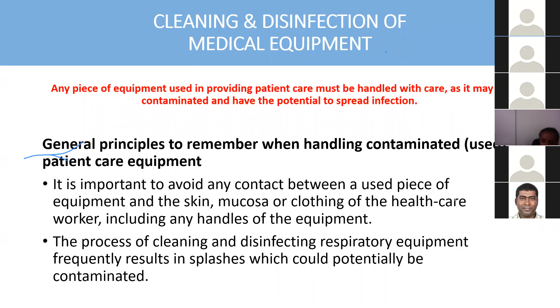Okay, general principle, remember when you're handling contaminated, used patient care equipment. Even though you think the clinician has cleaned all that, it's your responsibility as well to clean it before you do any testing and checks. Okay, so it's important to avoid any contact between the used piece of equipment and the skin, mask, and clothing of the healthcare worker. Basically, when the healthcare worker is going to clean, make sure they are using the proper PPE as well. Okay, because you don't want the healthcare cleaner to get infected as well. Okay, so the process of cleaning and disinfecting respiratory equipment is frequently exposed to splash, which could be potentially contaminated. Basically, fluid, all this touching the medical equipment. So we have to be careful with that.